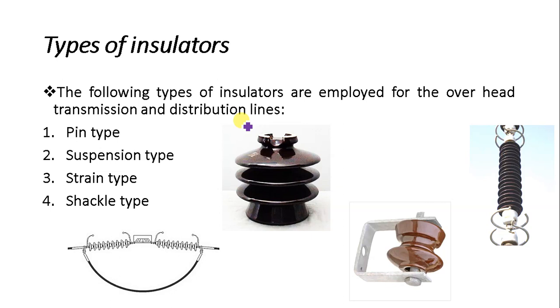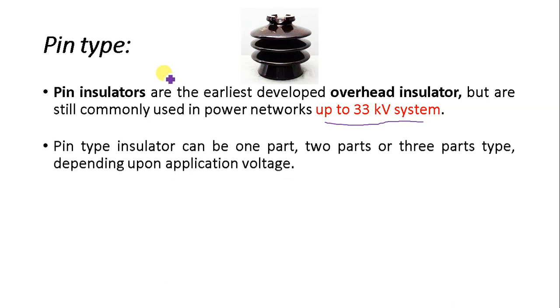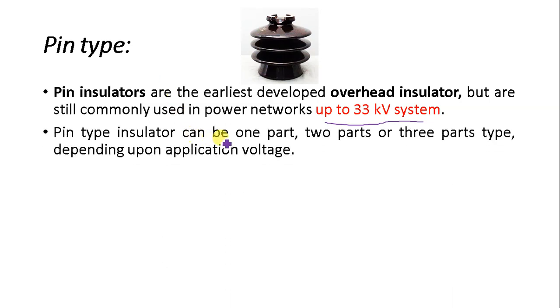If you like this video, feel free to subscribe to my channel and give it a thumbs up. Now let us first discuss the pin type insulator. These are the earliest development in overhead insulators, and that is why when the voltage is low we can use pin type insulators. When the voltage level is less than 33 kV, we can use pin type insulators.